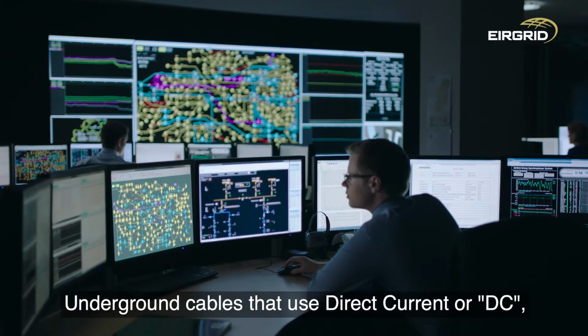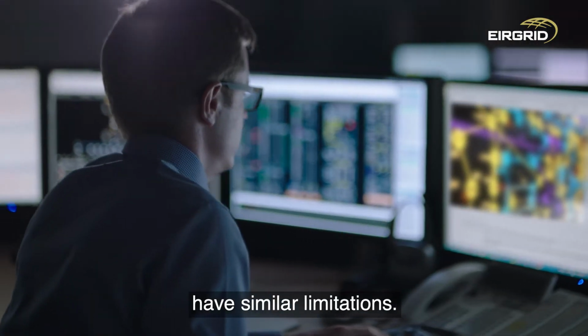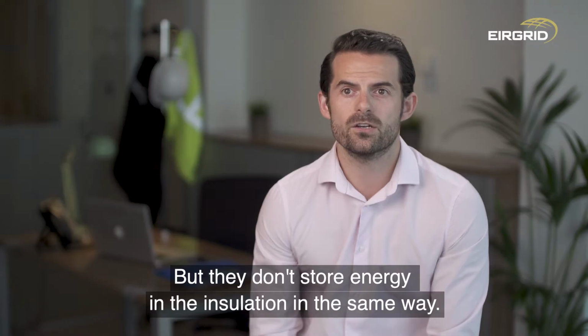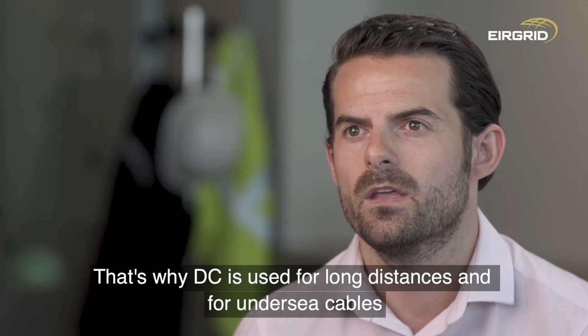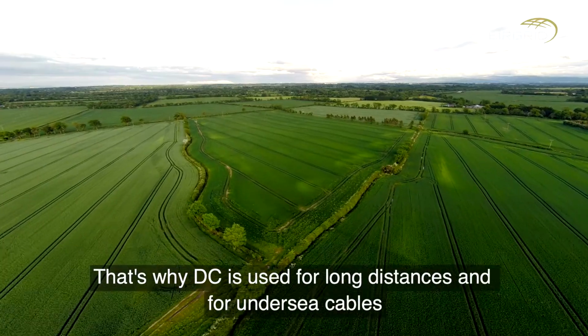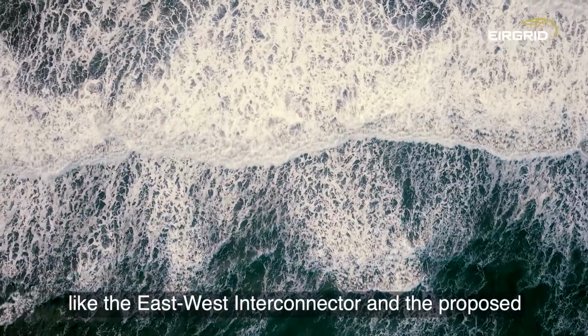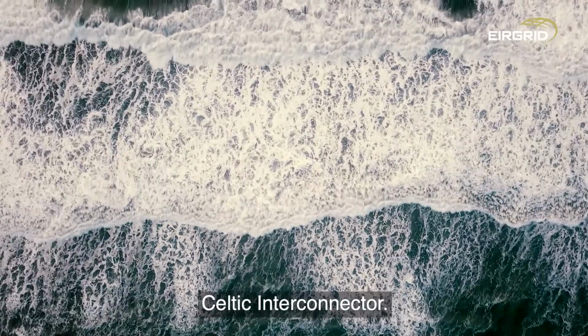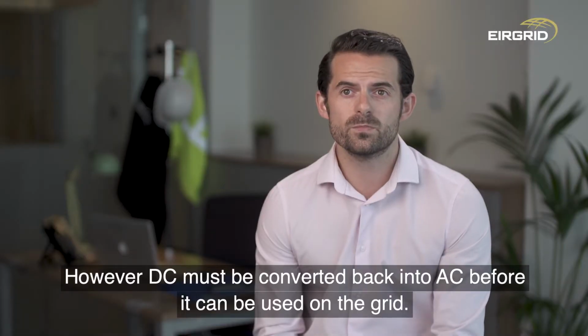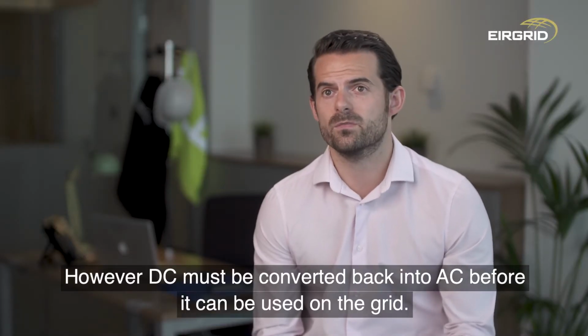Underground cables that use direct current or DC have similar limitations, but they don't store energy in the insulation in the same way. That's why DC is used for long distances and for undersea cables, like the East-West interconnector and the proposed Celtic interconnector. However, DC must be converted back into AC before it can be used in the grid.